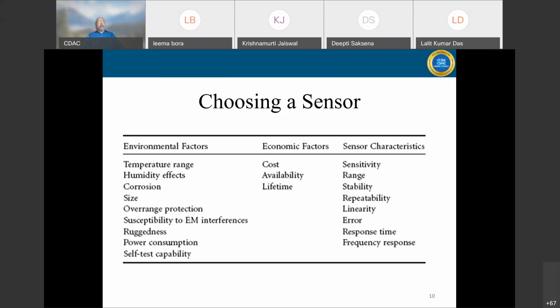Suppose you are using a temperature sensor where the temperature changes from 10 to 80 degrees. You check whether it's linear, whether the transduction mechanism can handle that bandwidth of variation in that parameter. Then there's error, the percentage of error in your readings. Then response time: if a temperature sensor takes 15 minutes to respond, but your process temperature changes every 1 minute, it may be very difficult to use that sensor. So response time is a major criterion, along with frequency response, whether the parameter value changing in seconds can still give acceptable readings up to a certain frequency.